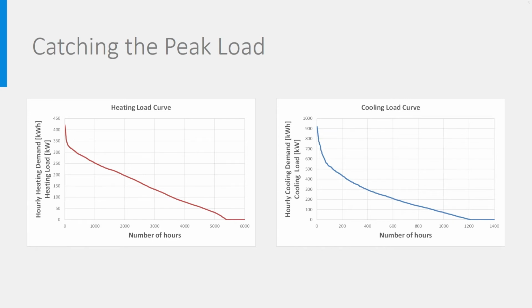Imagine we decide to design our generators to only 300 kW for heating and 500 kW for cooling. We are then missing the peak load. However, if we let the generator work longer at its maximum load, like that, we can store the missing quantity of heat and cold in a buffer and use it when needed.